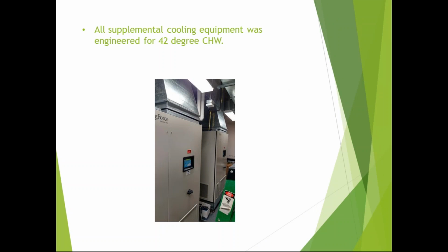All supplemental cooling equipment was engineered and designed for 42 degrees. Those are 5-ton units inside a space on the 6th floor. They're redundant units. Supplemental cooling designed for 42 degrees means that if I know, as a real engineer, a stamped mechanical engineer, that I'm going to get 42 degrees, I'm going to size my piping a certain way, how many rows of the coil I'm going to implement into that piece of equipment, what size chilled water supply valve I'm going to use to provide 42 degrees.